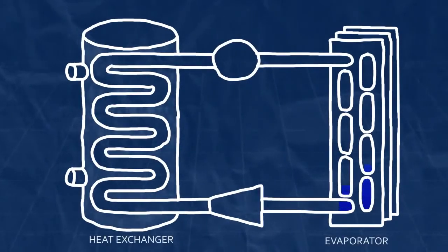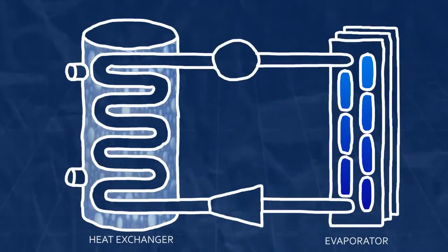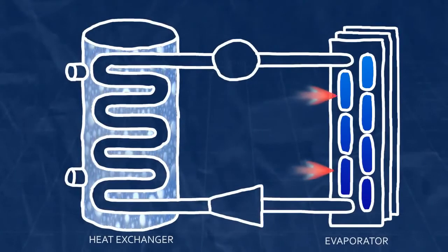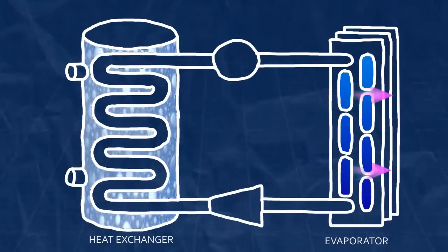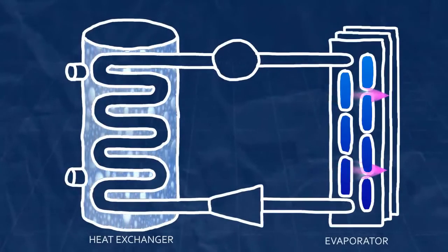In the beginning of a cycle, the refrigerant is in a cold, low-pressure, liquid-gaseous state flowing through tubes exposed to room air. It is colder than the room air, so heat in the air moves to the refrigerant. This is because heat always moves from warmer things to cooler things.